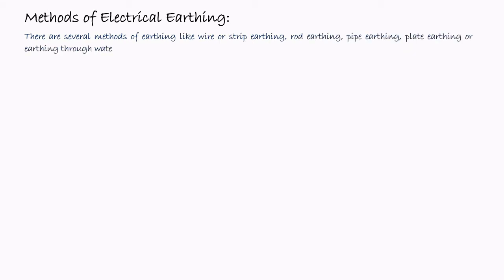Now, the methods of electrical earthing. There are several methods of earthing, like wire or strip earthing, rod earthing, pipe earthing, plate earthing, or earthing through the water mains. The most commonly used methods of earthing are pipe earthing and plate earthing. These are the most popular earthing methods that are generally used in normal applications.